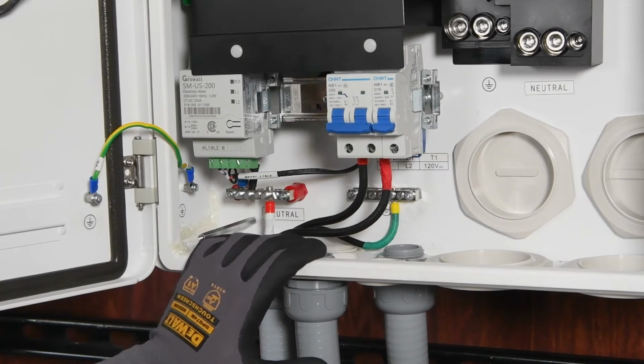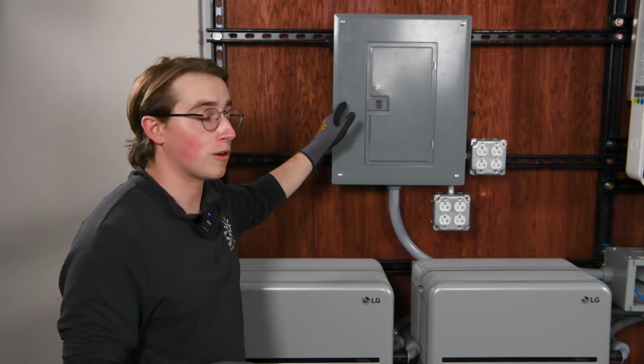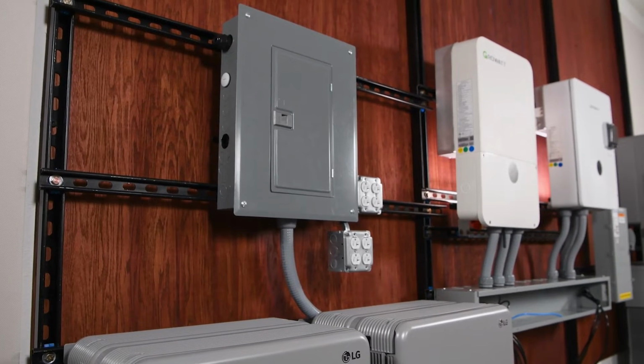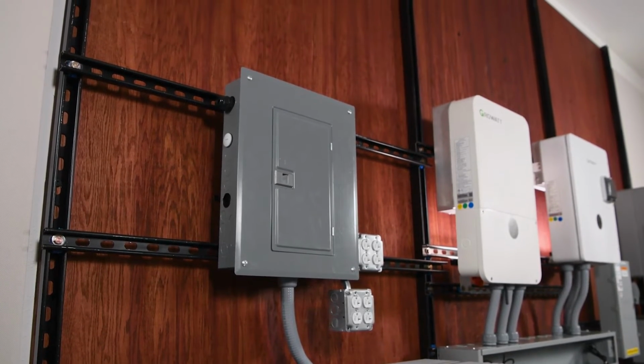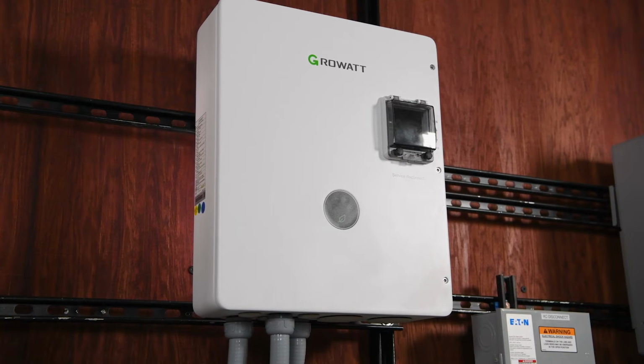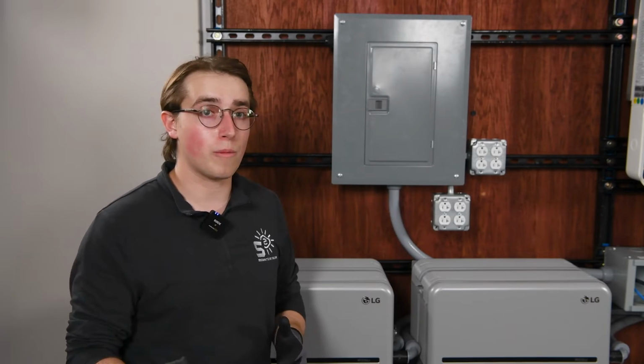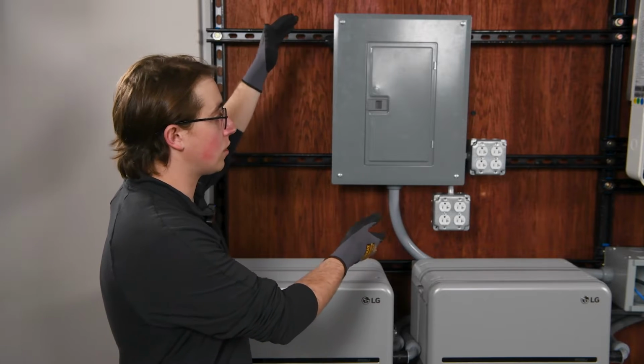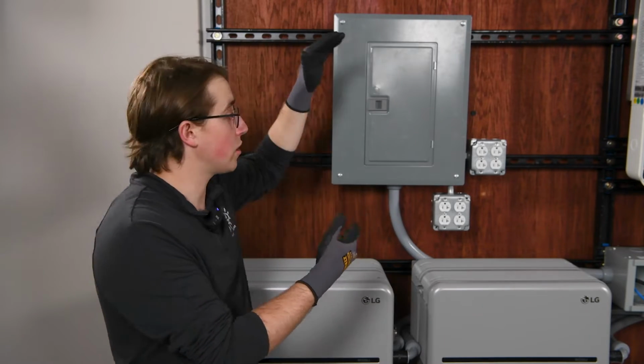For this install, we'll be using a smaller backup load panel, or our critical loads panel, and this will actually connect directly to the SYN, which we will wire up next. Now, if you're doing whole home backup, what you'll most likely have is a larger main load panel that is rated for 200 amps, which the SYN can fully support.